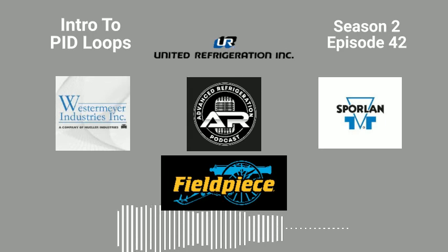Also make sure the valves you have aren't oversized for what you have, because that might affect your total PID adjustment as well. Any kind of modulating heat valves, anything where you're trying to control an analog value with an analog style valve, or varying output, right? Kevin was talking about a loop sequencer. Just to remind you guys, a loop sequencer is basically a control that takes an analog value, takes a set point, and tries to maintain that either with an analog output or a digital output, or it could be a bipolar stepper motor or something like that.